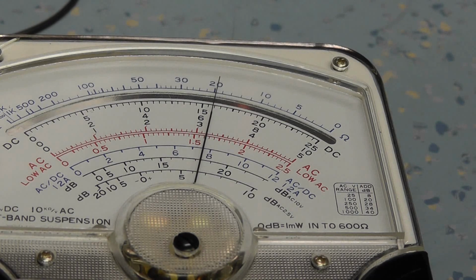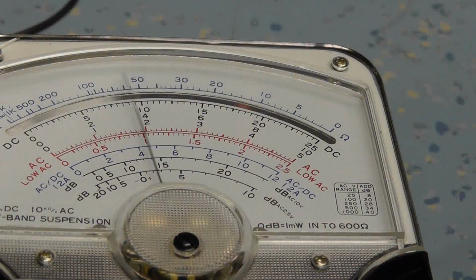20, 40, 50. Brilliant, that's working perfectly well. 60, 70, 80, 90, 100. Bear with me. That's 100. That's clearly working fine on that range. Let's go ×10 range. So let's go 100 ohms. There we go. 200, 300, 400, 500. That's working well as well.